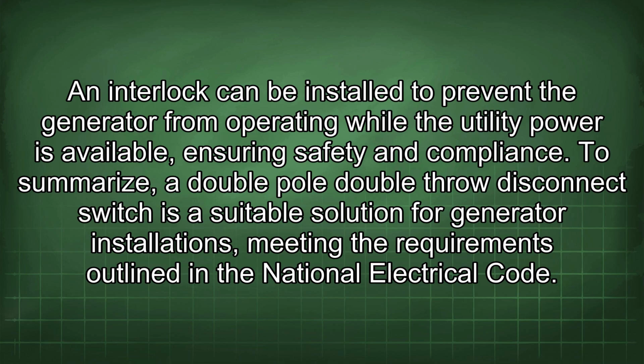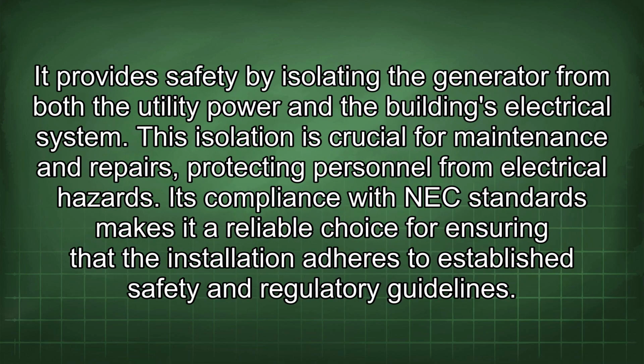compliance. To summarize, a double-pole double-throw disconnect switch is a suitable solution for generator installations, meeting the requirements outlined in the National Electrical Code. It provides safety by isolating the generator from both the utility power and the building's electrical system. This isolation is crucial for maintenance and repairs, protecting personnel from electrical hazards.